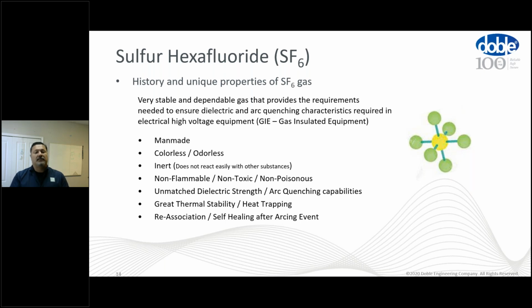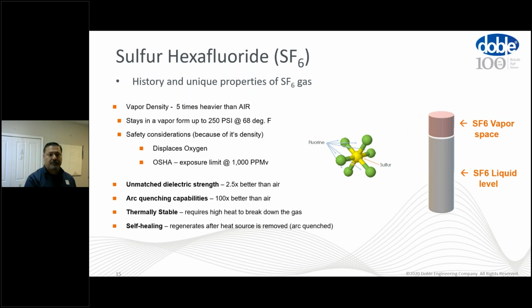It's got unmatched dielectric strength. It's got great arc quenching capabilities, great thermal stability, in other words, heat trapping, and reassociation. All these characteristics and components are what make SF6 such a great material for GIE. It can continue to isolate or insulate. It arc quenches and then regenerates itself without any real need, under normal operating conditions, of replacing the gas.